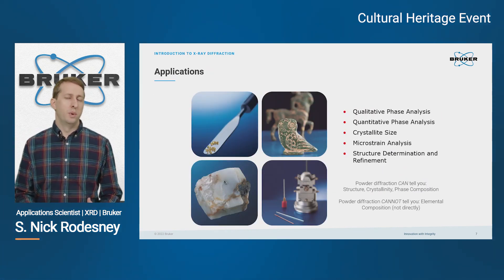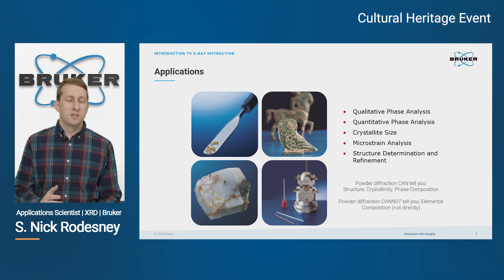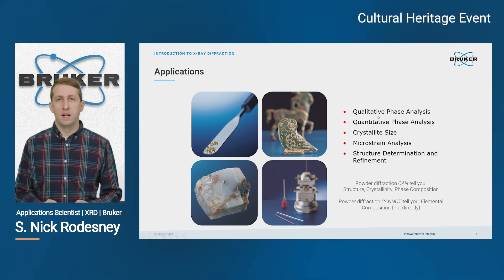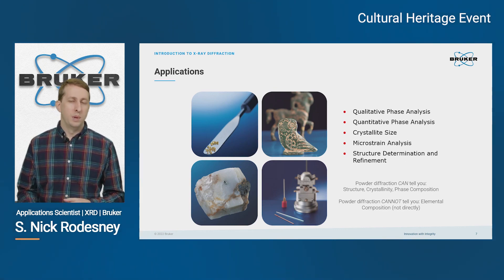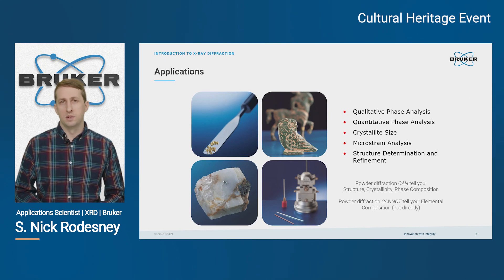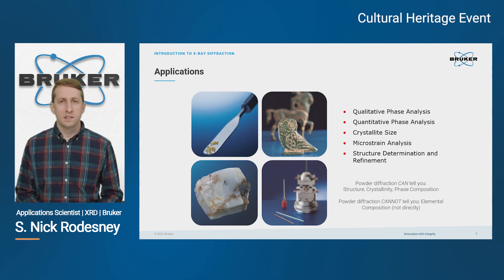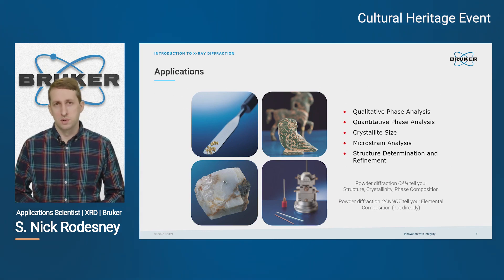So what can we do with XRD? Since we're probing the crystal structure of a material, we can answer the most fundamental question and determine if our material is crystalline or not. If we have a crystalline material, we can do qualitative phase analysis and identify the different crystalline components in our sample. Once we know what we have, we can do quantification. There are more advanced techniques that allow you to calculate crystallite size, if there's any microstrain built up within your crystal structure, and if you're synthesizing new compounds, you can even solve crystal structures using XRD.